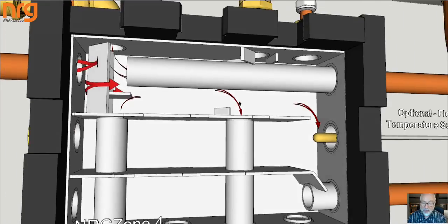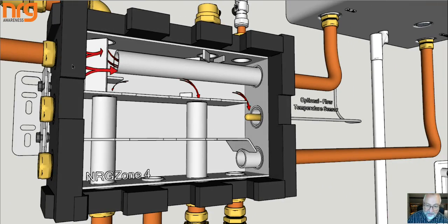So let's say it flows back down around this plate if that pump is calling, and heats the underfloor in this example. It can also go down if the pump on the radiator is on, and it'll draw that water down. So that would have any surplus energy that's coming through from the boiler that isn't being taken by the hot water, plus it'll have the delta T reduced water coming back from the cylinder circuit.